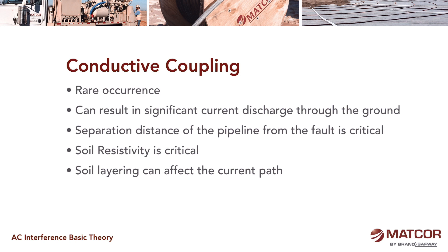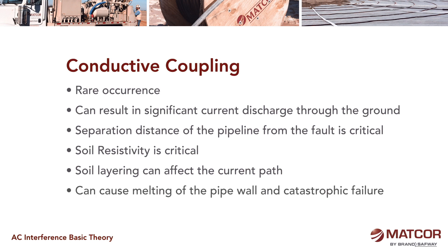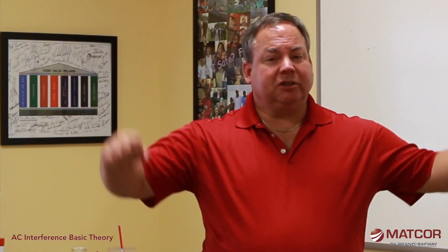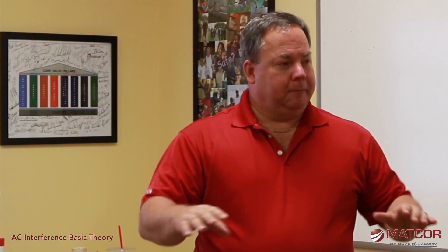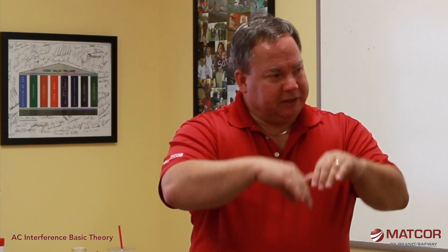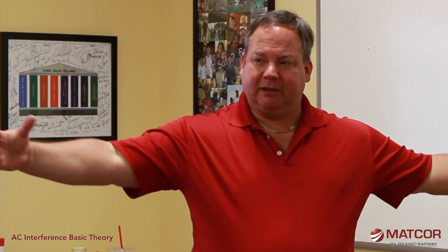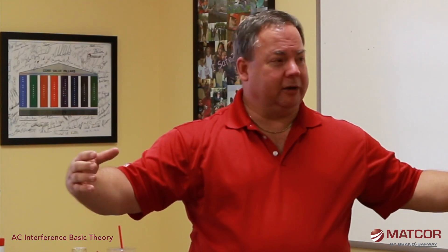Arcing is not easy to occur and is relatively rare, but it would cause melting of the pipe wall and catastrophic failure. The other issue with conductive coupling is that when all this current is discharged into the earth, we have what's called a voltage rise in the earth. From the point where the current is being dumped, you get this voltage rise that radiates outward — highest voltage in the middle — and the further out you get, the less the voltage.